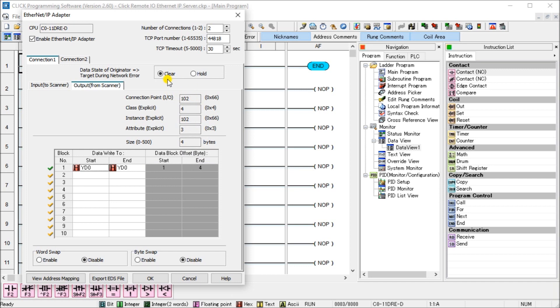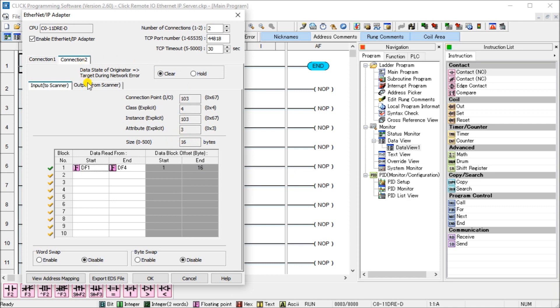Notice we've hit Clear so if communication is lost using EtherNet/IP, it will clear or zero those inputs and outputs. On Connection 2, the input connection point defaults to 103. We have our analog inputs DF1 to DF4 — 16 bytes of information. On the output side we have DF5 and DF6, which are the output analog values, going from byte 1 to 8, so eight bytes of information there.